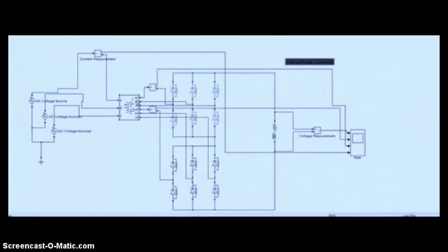Now if we OK this one, we want to measure the current so that we can see what is the advantage of using 2 secondaries, 1 in Y and 1 in delta. The obvious advantage is this, that if we connect our transformer like this, it gives a delay of 30 degree at the secondary. That can be used to make this 12 pulse converter. We also claim that if we use this, the input line current has the lowest order harmonics that appear at the 11th and the 13th. So let us see how we have connected it.